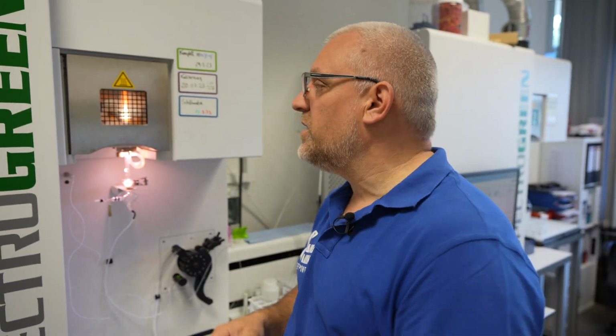In the older machine, this does not happen this way, so we have a few problems with irregular testing, and that's why we use that machine only for reverse osmosis. The new model also has about 10-15 years of development in optics and camera systems, and they are perfectly made for seawater. Nowadays we come down to a minimum detection level that is 10 times lower than the standard machine we had before. That means we get low enough to show elements in relevant amounts, so that we know, okay, we have this amount in, and if it's under, usually it's not necessary to know if it's lower or not.